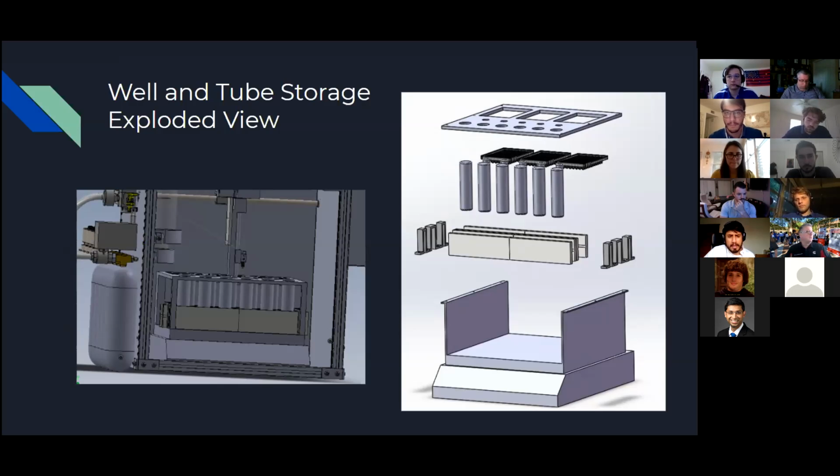And lastly, stuck to the case of the incubator? Can you repeat that? They're just stuck to the case of the incubator? They're stuck to the tubes themselves. Oh, to these tubes themselves. Okay, so they're directly heating the tubes. Yeah, which I don't see as an issue since the melting temperature of glass is way, way higher. Oh, sure.